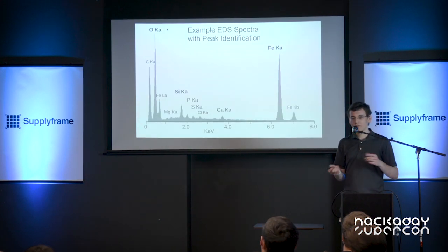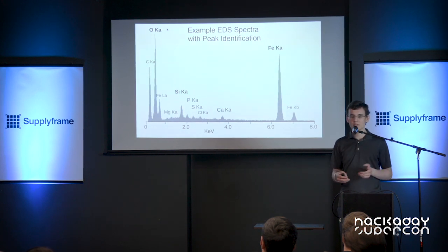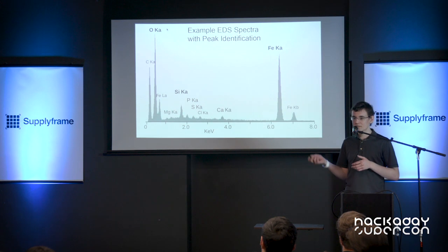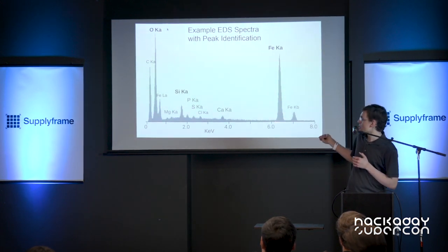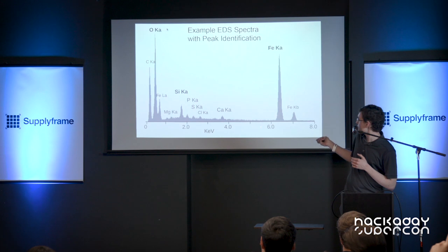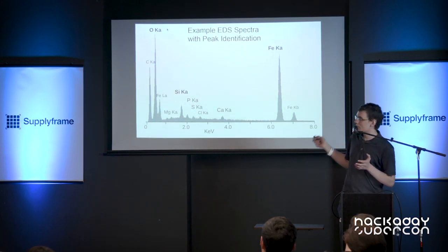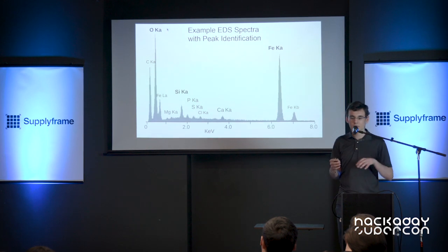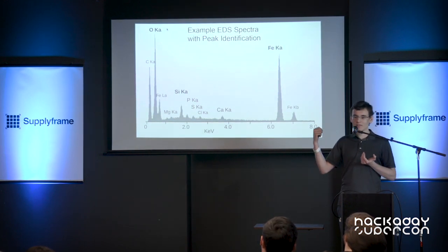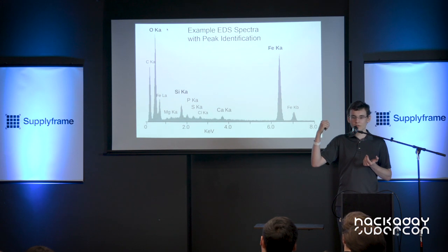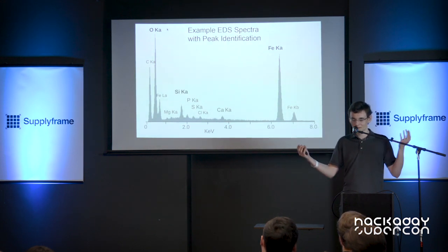To look at characteristic X-rays, you need something called energy dispersive spectroscopy, or EDS. This is an example EDS spectrum. You can see a peak for iron right past 6 keV, and another peak for oxygen. The K-alpha next to it just means it's the X-ray that comes from the outer layer of that atom. Using that, we can tell we probably have some rust on the surface of whatever the sample is — because iron oxide.